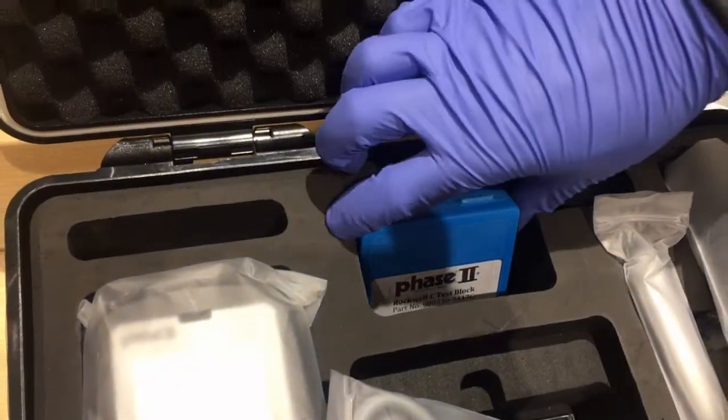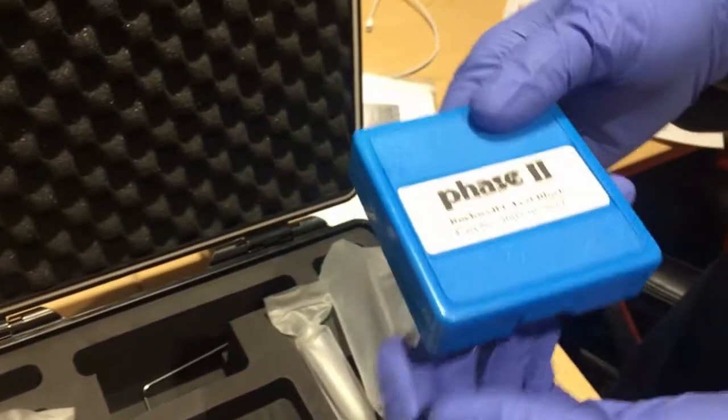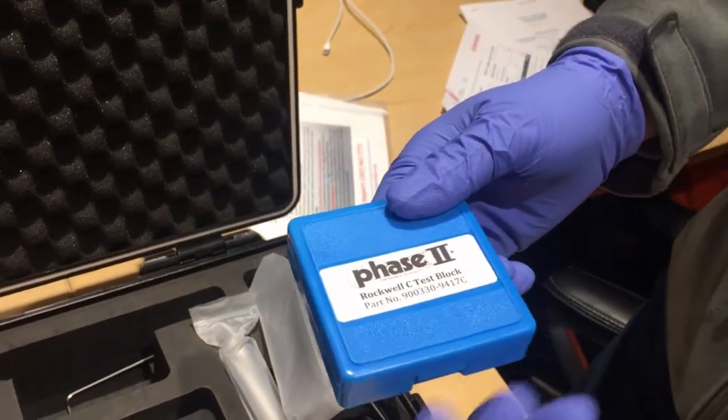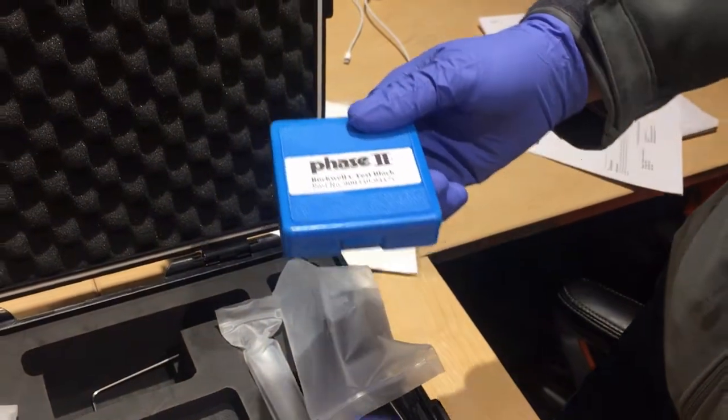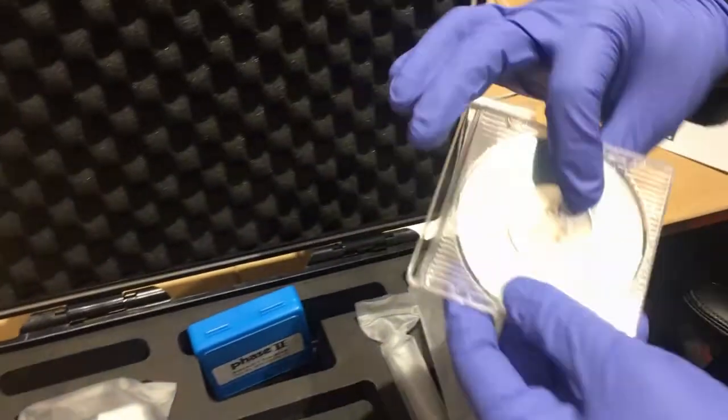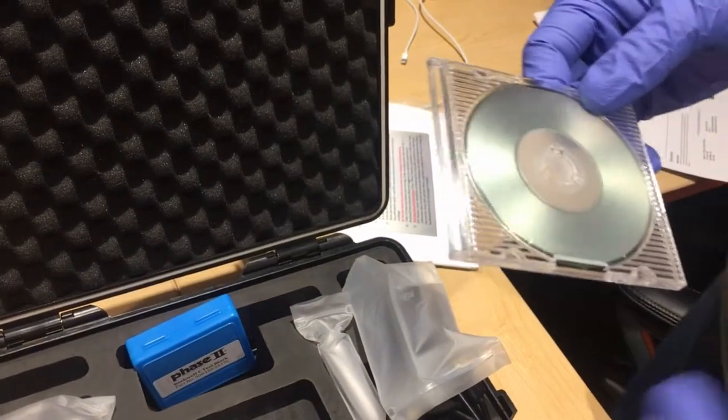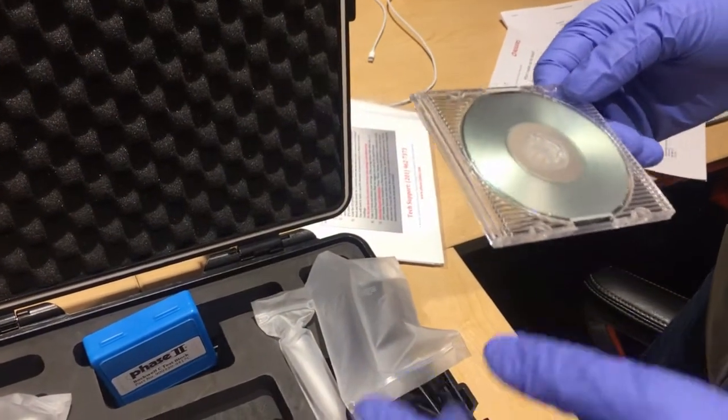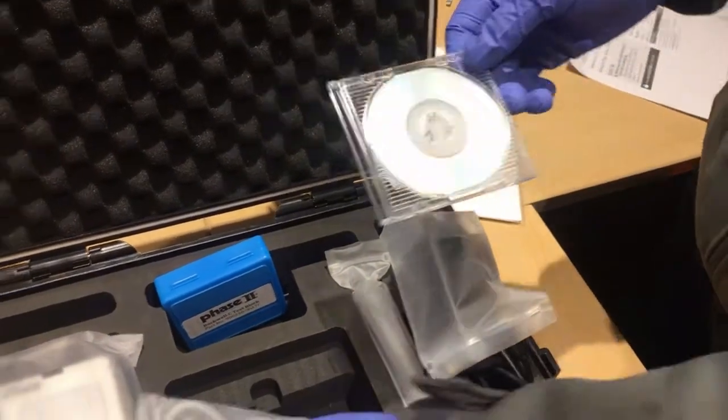Here is the test block. It has a standard hardness there, so we can calibrate our new product. And here is the disk. This disk allows you to utilize the software on your PC in order to transport your data from the machine to your PC.